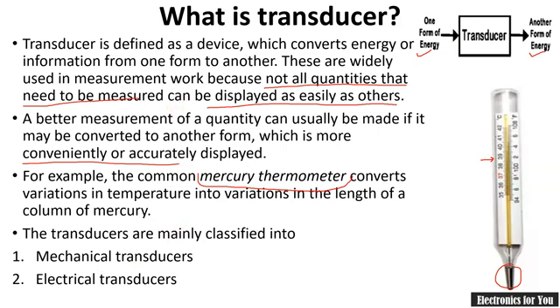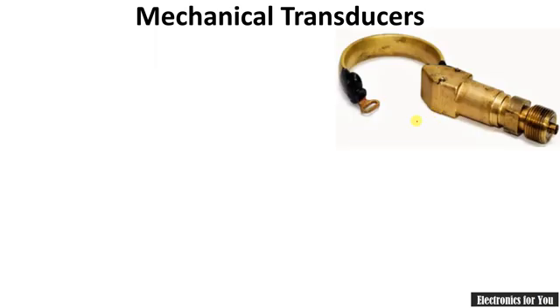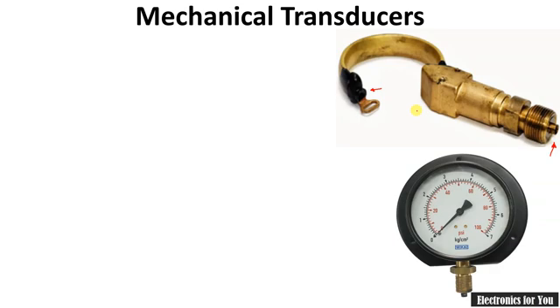Transducers are mainly classified into mechanical transducers and electrical transducers. A simple example of a mechanical transducer is the C-type Bourdon tube, which converts input pressure — for example from a fluid — into displacement. The pressure tries to make the C-shaped Bourdon tube straight, and therefore it converts pressure into displacement.